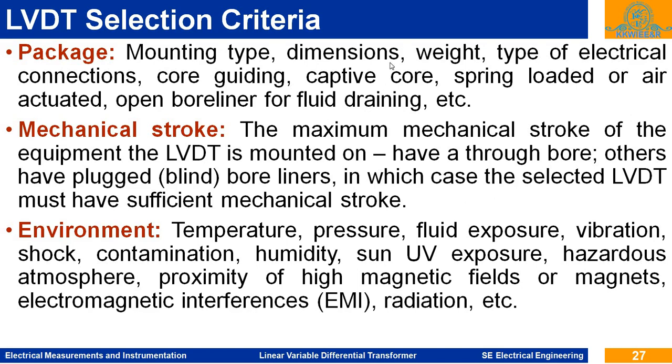The overall dimension, the space arrangement on that particular machine, the weight, type of electrical connections, core guiding, captive core, spring loaded or air actuated, open bore liner for fluid draining, etc. You must specify this, depending on the size or space on the machine.